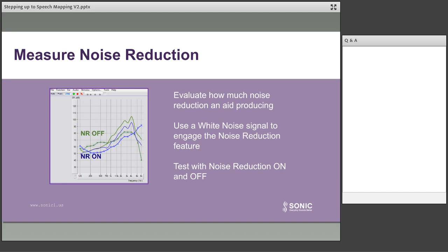You can measure noise reduction. Now, every manufacturer does noise reduction differently. They apply different amounts of gain reduction based on the identification of noise. And so this is a very easy test to do. You do one run with the noise reduction turned on and one run with the noise reduction turned off. And the difference just lets you know what's happening with the noise reduction at that time. So say if you've run it for one model, for one manufacturer, at least now you have an idea when they say medium, what's actually happening in the hearing aid in terms of its ability to reduce noise.